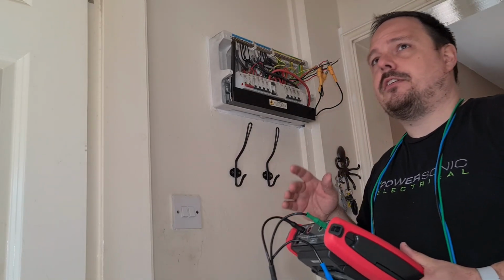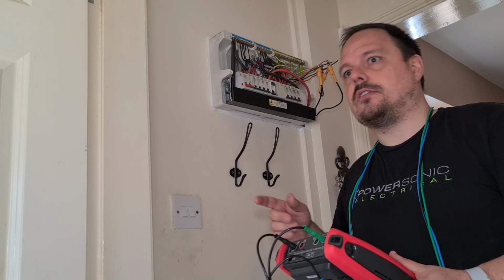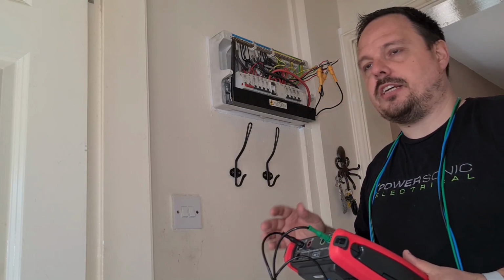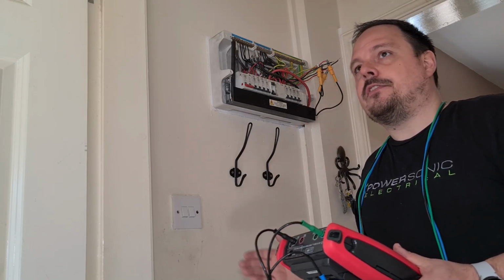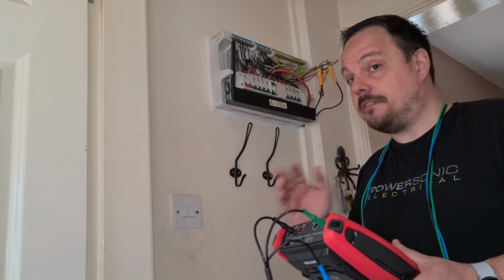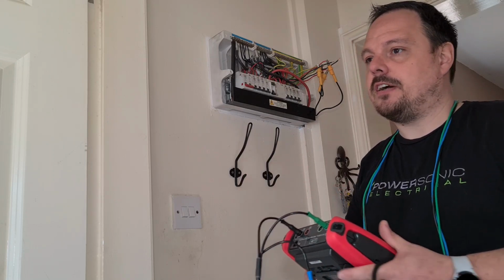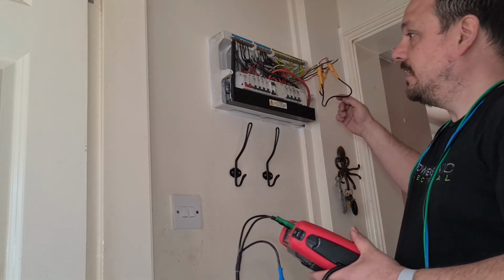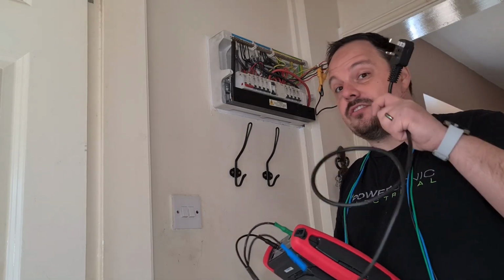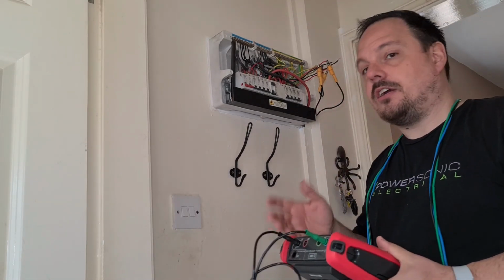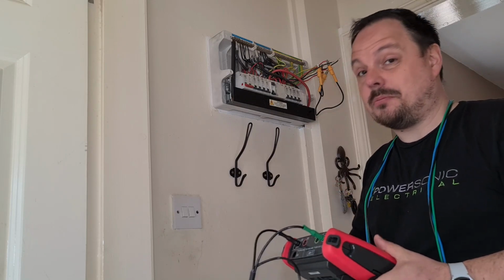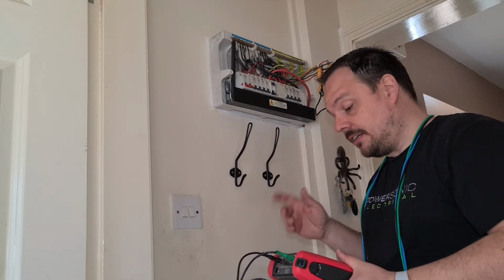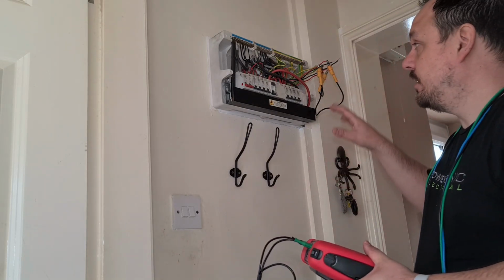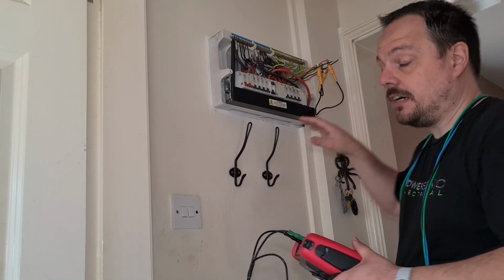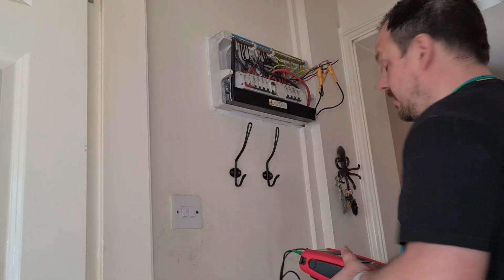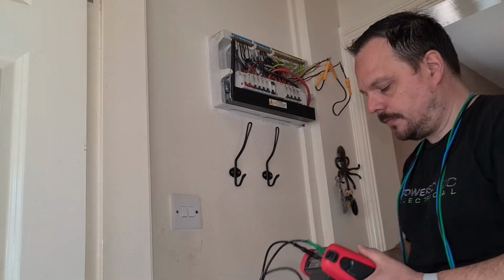I think roughly speaking, if you added little r1 to little r2, you were around 0.6. If you make that division by 4, you're sort of around 0.15. And then we said there's all the tolerances in these extra little bits of leads, the terminations through the socket front itself. They're all going to have a small impact, and that's a pretty acceptable value. So that's the big R1 plus big R2 on this very, very small little ring final circuit, which literally just jumps to my right hand side and goes around the utility room.